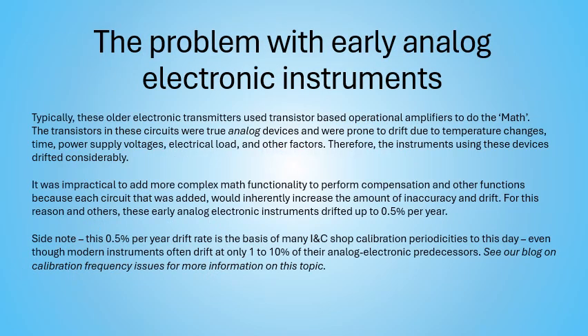So as I said, typically these older instruments use transistor-based op amps to do all the math, and they obviously drifted a lot due to temperature changes, just over time. Power supply voltage would have a big impact. Power supply warming up would have a big impact, or the transmitter itself as it stabilized temperature. The electrical load, so depending on how many milliamps and what the load on the transmitter was, and many other factors. So these instruments drifted considerably.